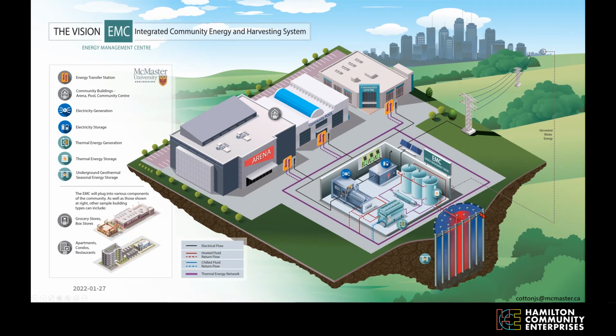Well, we have built the system with seasonal storage. At McMaster, we have a 66 borehole thermal storage system. It goes down 7 stories, 30 meters in diameter, and we actually heat up the ground to 60 degrees Celsius during the summertime. In the wintertime, we use that heat directly during peaks. If you manage this properly, you start reducing the peak even on a minus 40, minus 30 degrees Celsius day, really integrating our different systems.